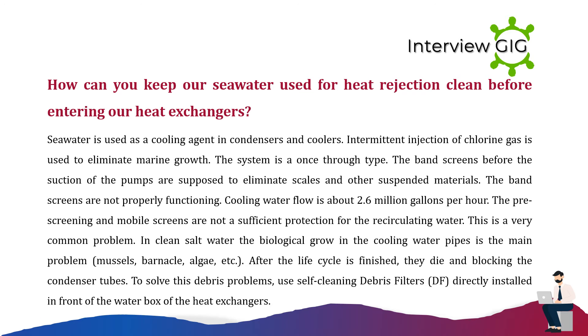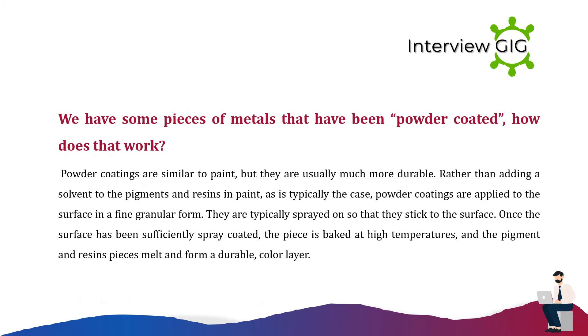How can you keep seawater used for heat rejection clean before entering heat exchangers? Seawater is used as a cooling agent in condensers and coolers. Intermittent injection of chlorine gas is used to eliminate marine growth. The system is a once-through type. Band screens before pump suction are supposed to eliminate scales and other suspended materials, but they are not always properly functioning. Cooling water flow is about 2.6 million gallons per hour. Biological growth in cooling water pipes — mussels, barnacles, algae — is the main problem; after their life cycle they die and block condenser tubes. To solve this, use self-cleaning debris filters (DF) directly installed in front of the water box of the heat exchangers.